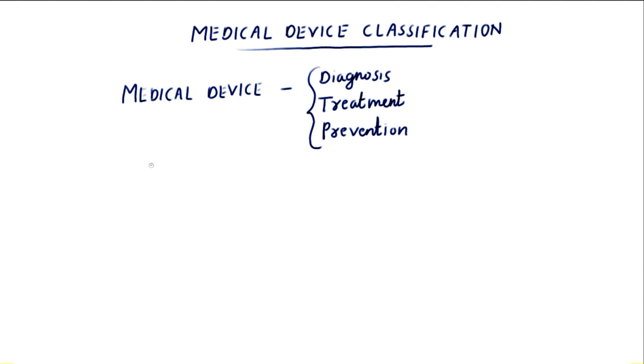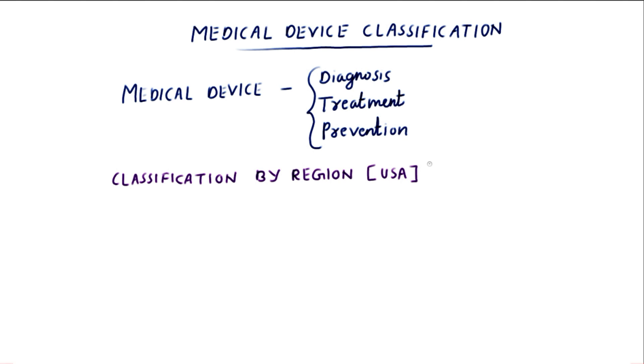FDA recognizes three classes of medical devices based on the level of control necessary to assure safety and effectiveness of the device, or based on the risk involved when it is used in the patient. FDA established classification of around nearly 1,700 different medical devices based on the intended use and risk involved. As the risk increases, the level of regulatory control also increases.